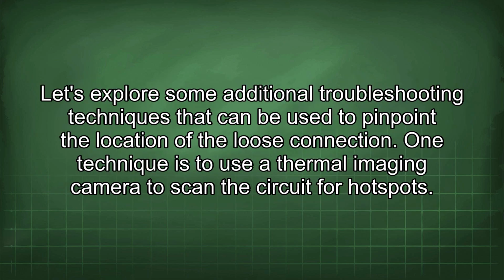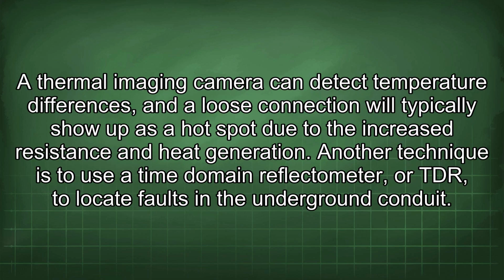Let's explore some additional troubleshooting techniques that can be used to pinpoint the location of the loose connection. One technique is to use a thermal imaging camera to scan the circuit for hotspots. A thermal imaging camera can detect temperature differences, and a loose connection will typically show up as a hotspot due to the increased resistance and heat generation.